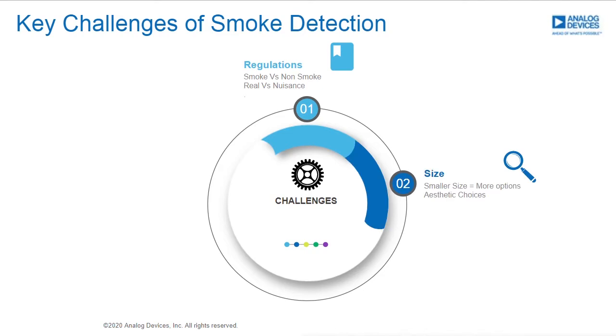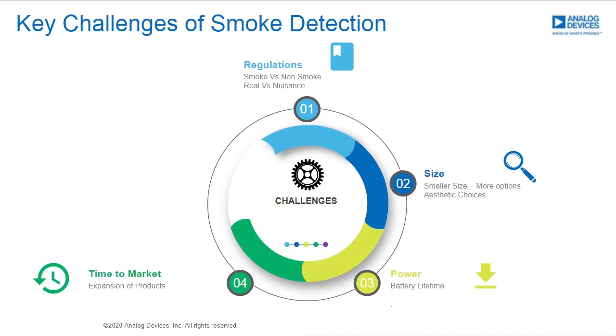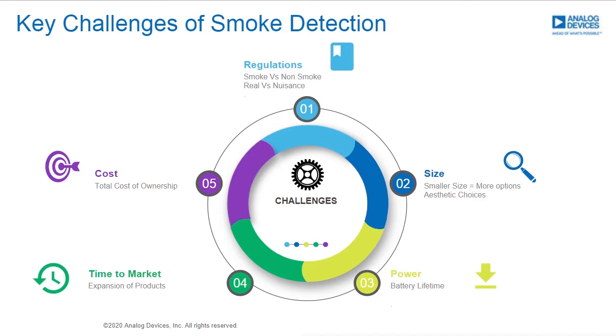As smoke detection moves from standalone to connected network devices, size is an important factor. Customers are looking to change the design aesthetics of traditional smoke detectors, as well as place smoke detectors in harder to reach locations, such as in transportation. Aligned with size is power, where better detection is now required for less power. In batteries, it means either smaller batteries or longer life with the same battery. On mains powered, it means being able to add more detectors on loops like 4020. And then finally, there's the challenge of getting to market quickly in light of time-bound regulations and understanding the total cost of ownership, not just from a bill of materials, but from a manufacturing and platformization benefit. So I'm now going to pass you over to Kevin to bring you through the next section.